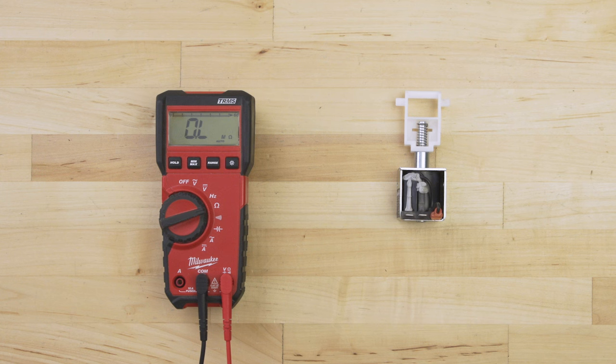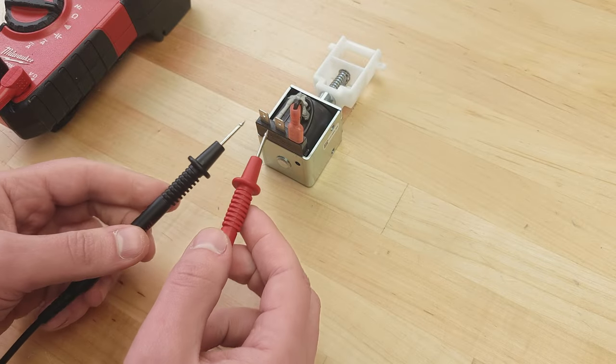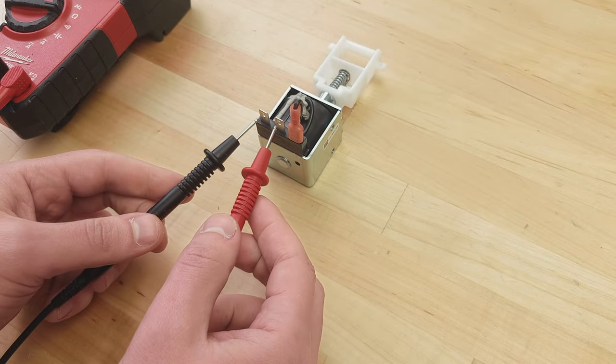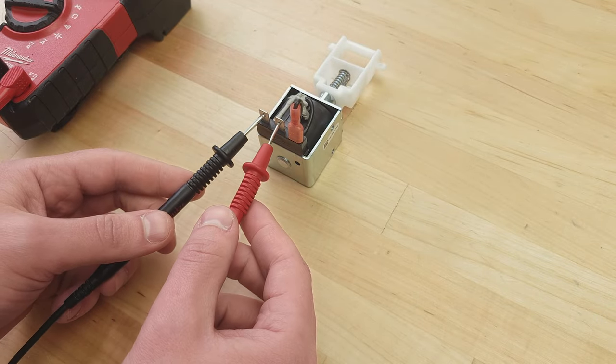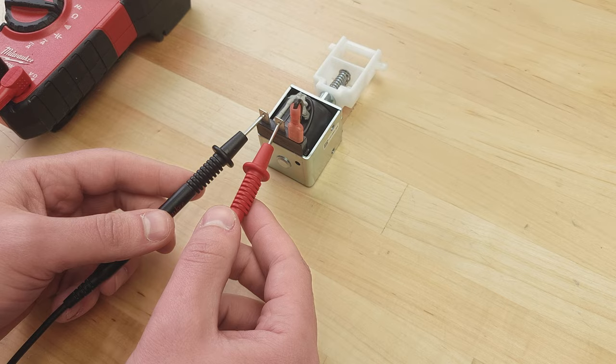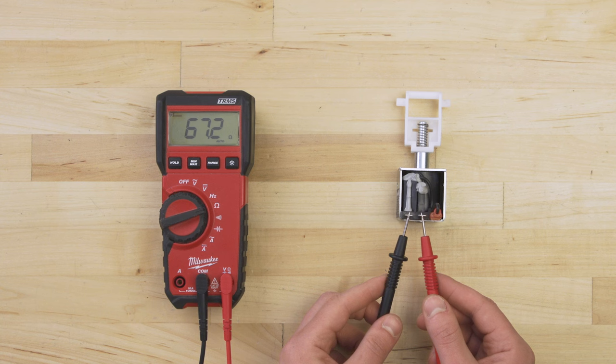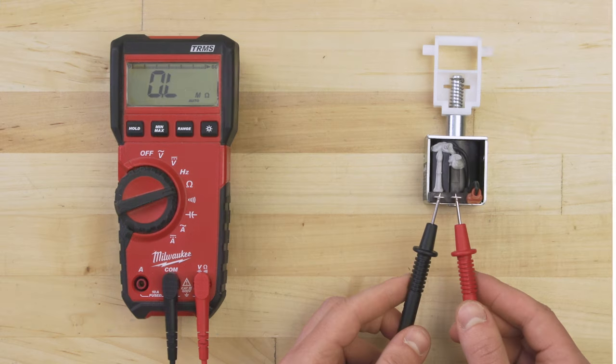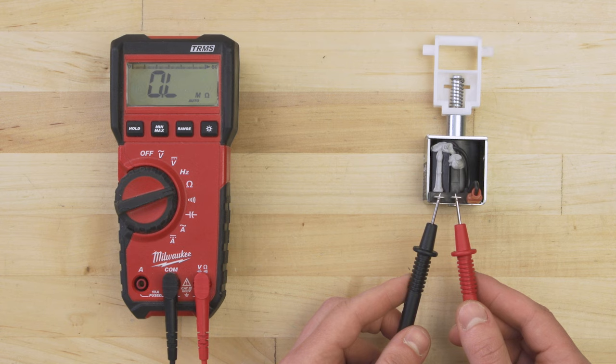Set your multimeter to the ohms or resistance setting. Now touch the probes to each terminal. There should be a resistance reading of around 20 to 100 ohms. If there is no resistance or no continuity, then the solenoid has likely failed electrically.